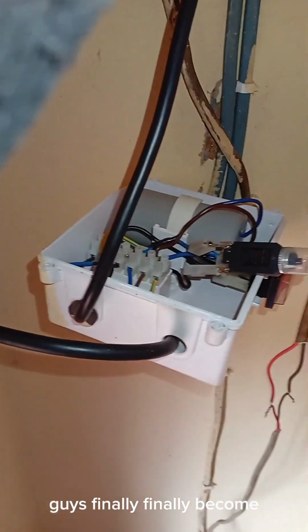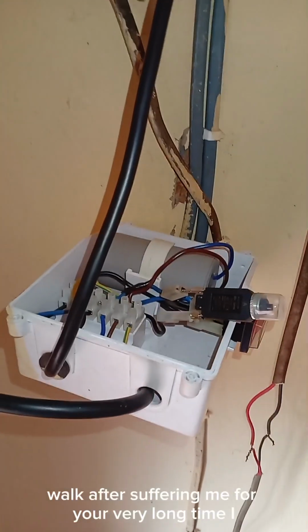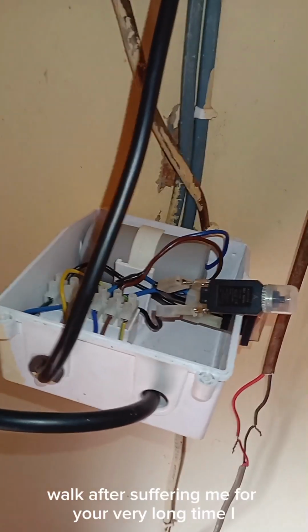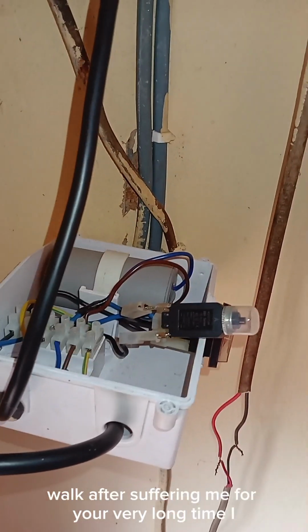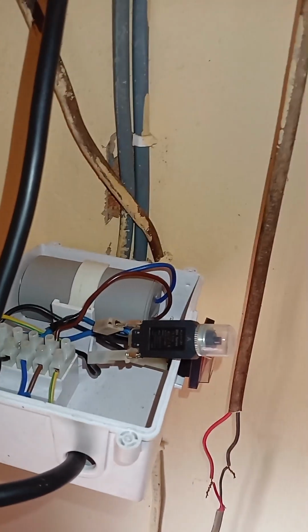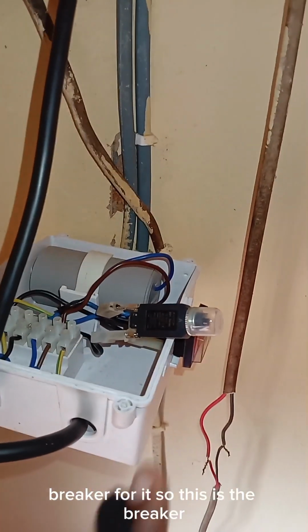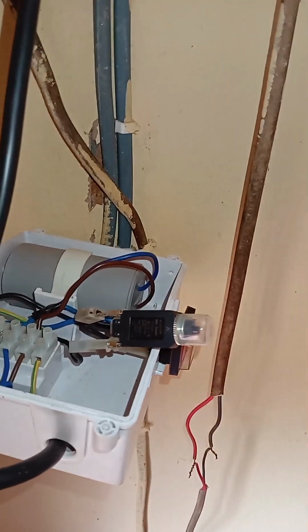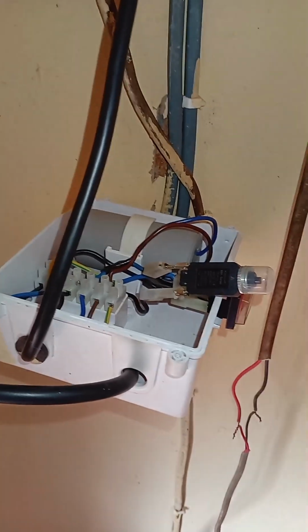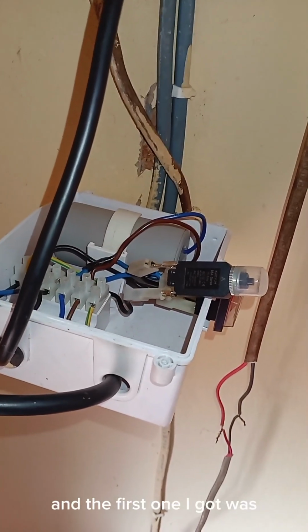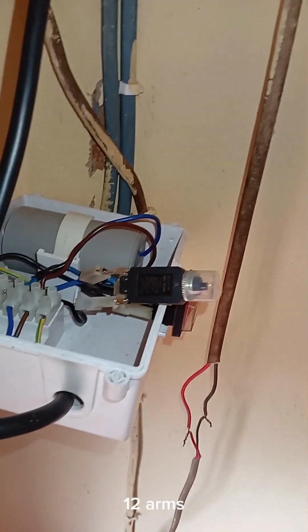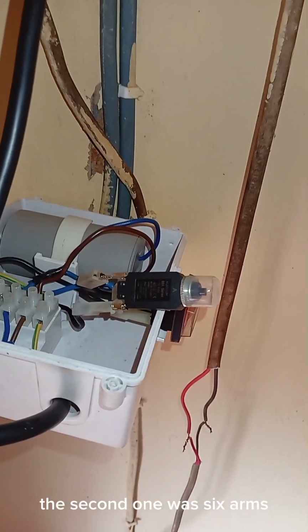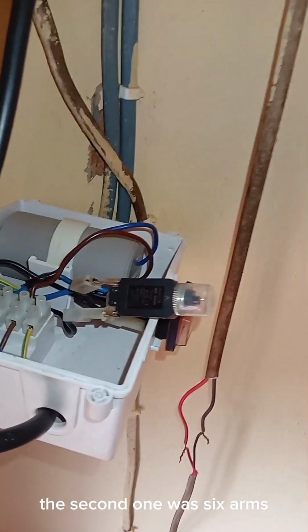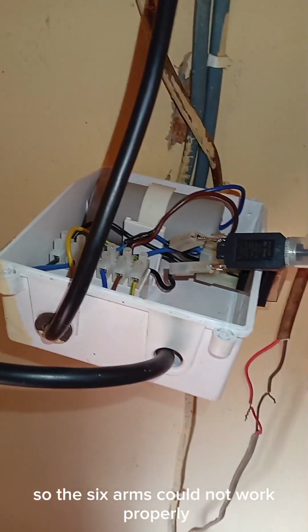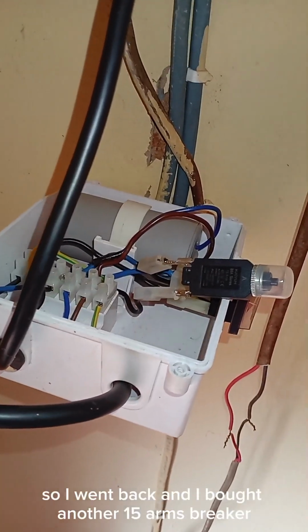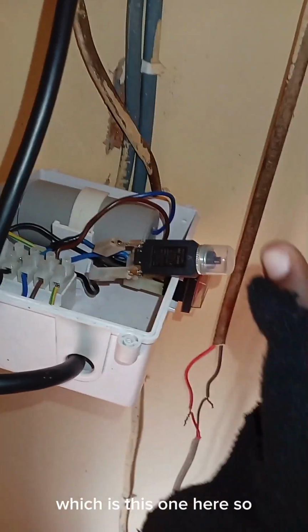Guys, finally the pump worked. After suffering me for a very long time, I got 2 breakers for it. This one you are seeing is the breaker. The first one I got was 12 amps. The second one was 6 amps. The 6 amps could not work properly. So I went back and I bought another 15 amps breaker, which is this one here.